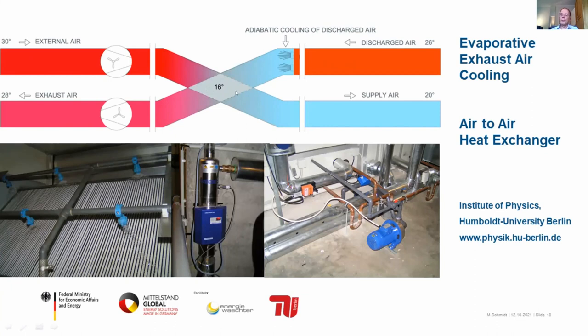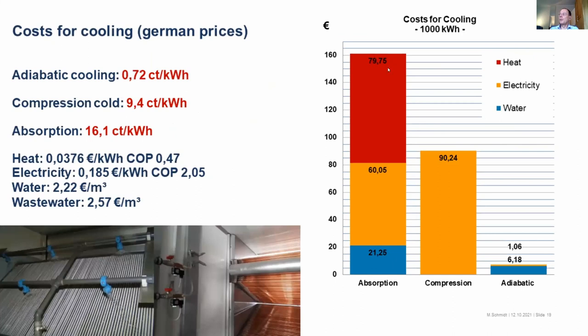And this is a really efficient system. We compared the operating costs for three different cooling production methods. For an absorption chiller, which in former times was the more efficient idea of using cogeneration, producing cold in summer out of heat from cogeneration - but it's the most expensive way to produce cold, costing about 16 cents per kilowatt hour. Compression systems in this building cost about 9 cents, but evaporative exhaust air cooling costs 0.7 cents. And if you're using rainwater, you can even save the energy and operating costs for water - then you pay about 0.1 cent per kilowatt hour.